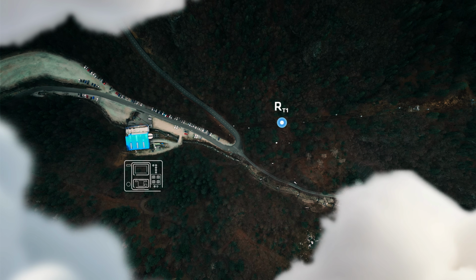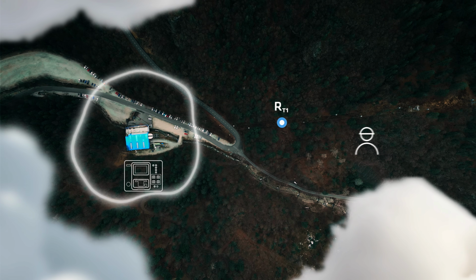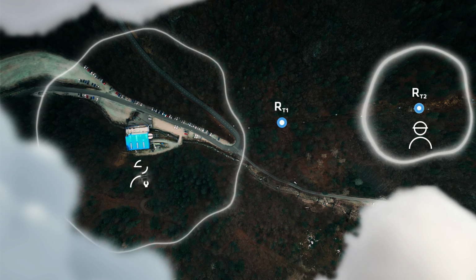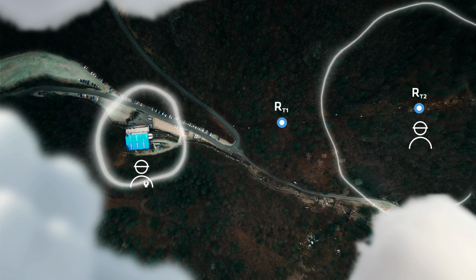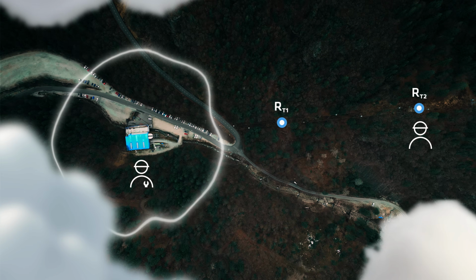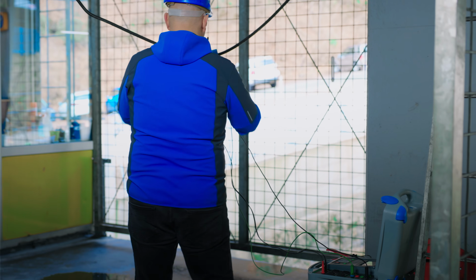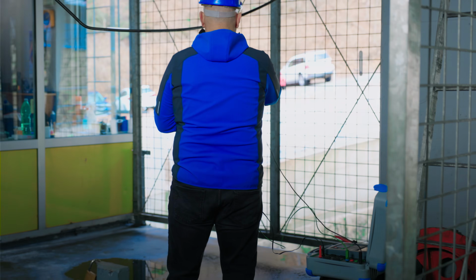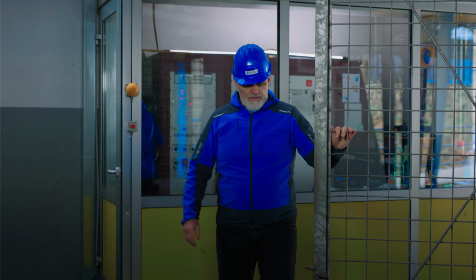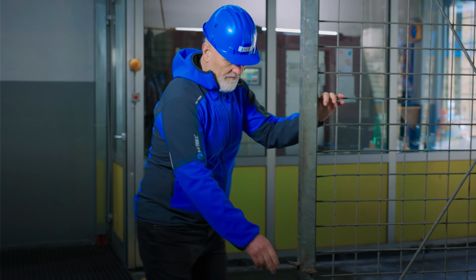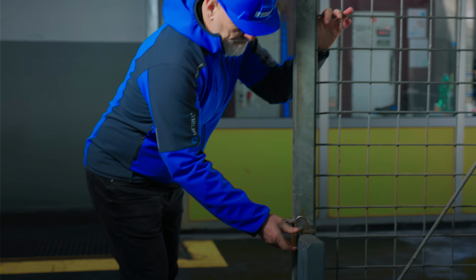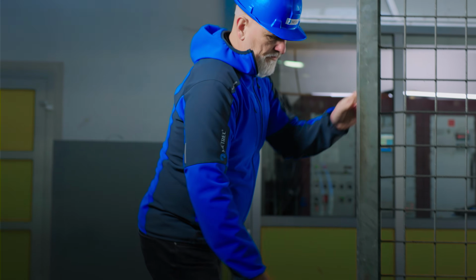In both cases, every tower is tested to measure its resistance to Earth. The entire line of towers can be completed in less than an hour. This is a significant improvement compared to the traditional approach, which involves walking from tower to tower during hot summer days, while carrying heavy loads, reels, and probes for several days.